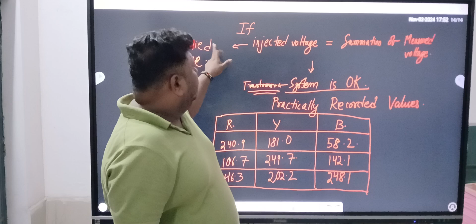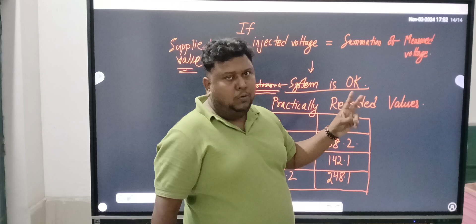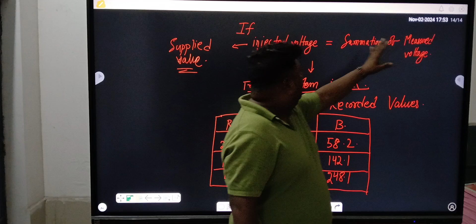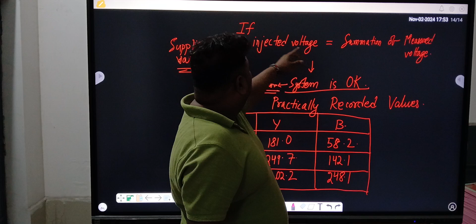What is the measured value? If I am giving the supply to a particular phase, there are two phases left out. Those two left out phases are measured with respect to earth, and that measured voltage is known as the measured voltage. So the summation of those two measured voltages should be equal to the injected voltage. This is the condition. Under this condition only we can declare that the system is okay, or the transformer is okay, or the core of the transformer is okay. This is known as the magnetic balance test.